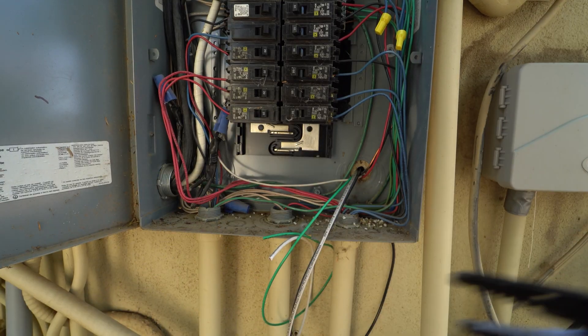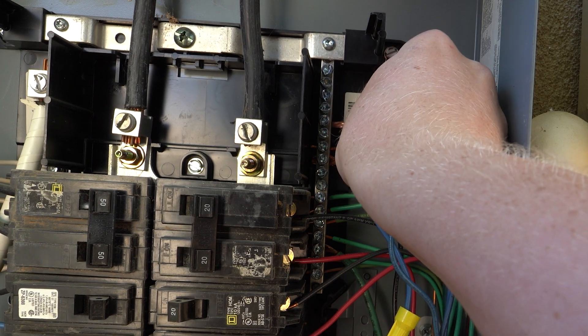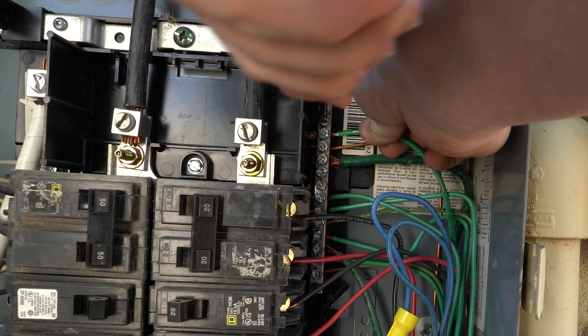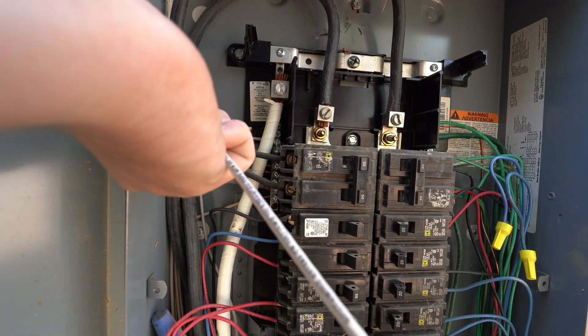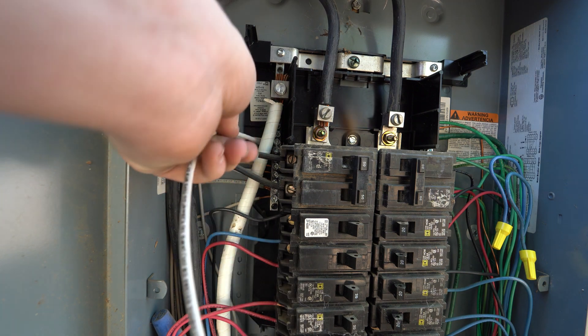Once the wires are ran into the electrical box, cut them to length. Locate the grounding bar, which will likely have green or copper wires already in it. Loosen a screw and add in the green wire from your electrical outlet. Now install the neutral wire into the neutral bus bar.